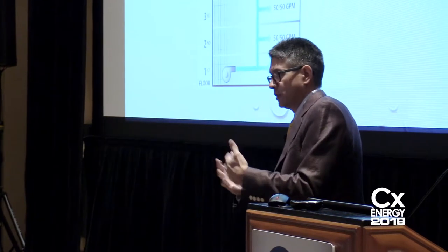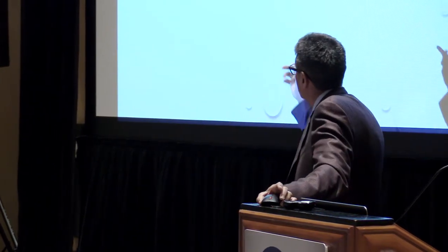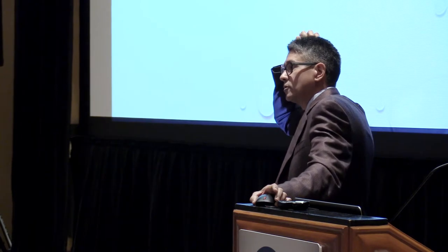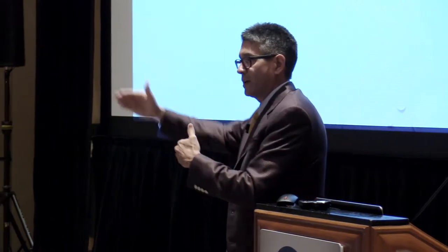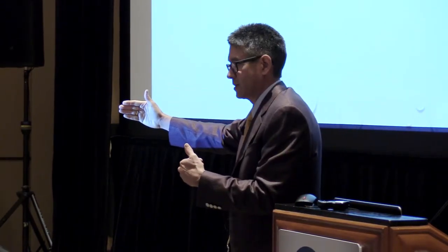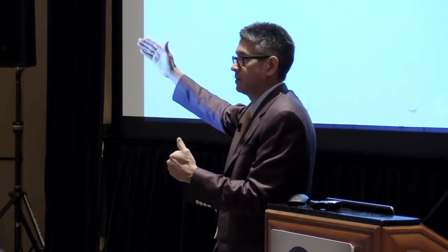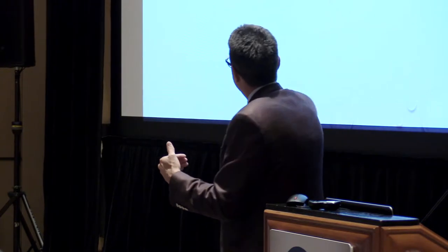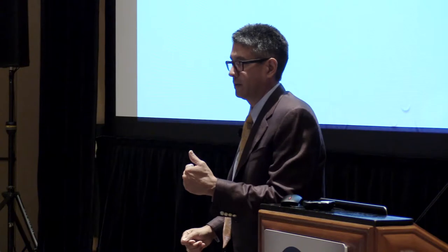I had to have an engineer explain to me what he really was looking at. When he said let's balance it to diversity, he was basically saying set all your valves to the percent diversity of water flow for the system. He looked at that other example, laying it out on the job, and said, well, shoot, if I just cut them all back, now I can get water flow to all my valves. And we're like, okay. So he said, if I have 50 GPM at that floor, let's set it for 33. And we started going through and setting it up.